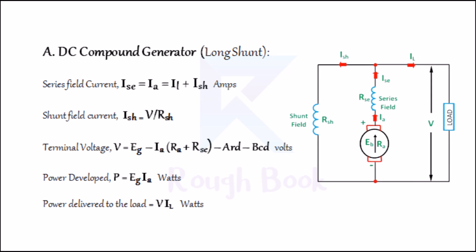8A: Long shunt DC compound generator. Depending on how the series field winding is connected to the shunt field winding, we have long shunt compound generator and short shunt compound generator. In the long shunt DC compound generator, series field current ISE = IA = ISH + IL. Shunt field current ISH = V / RSH. Terminal voltage V = EG − IA(RA + RSE) − armature reaction drop − brush contact resistance drop in volts. Power developed P = EG × IA in watts. Power delivered to the load = V × IL in watts.